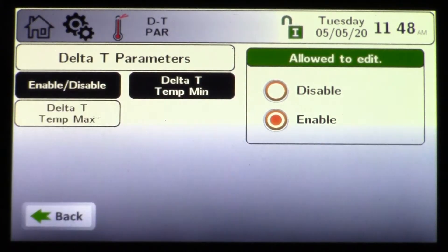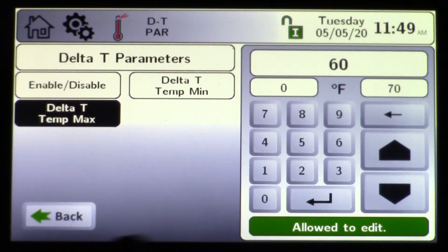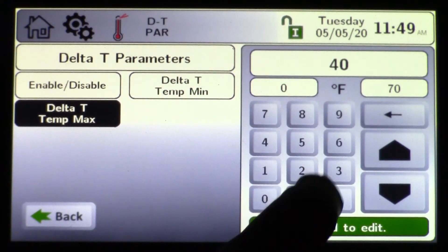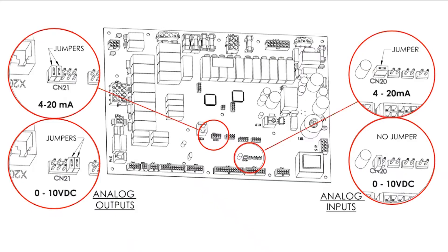The delta T parameters are here. You can enable or disable for the delta T minimum or the delta T maximum. The maximum we would ever allow on this product — the Magnotherm 5:1 — is 70 degrees. Here on the screen we're showing the zero to 70 degree maximum delta T. In my example I'll choose 40 degrees for the maximum delta T.